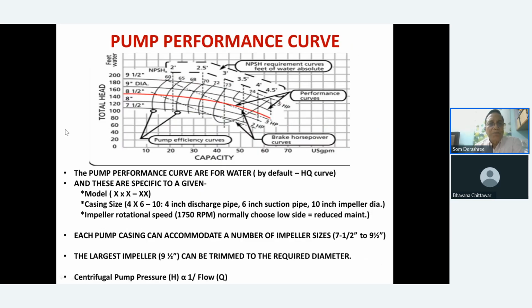Now, what are the pump performance curves? Pump performance curves are basically HQ curves, which also give you efficiency. These are all the curves for different diameters. This is 9.5 inch diameter, this is 9 inch diameter, 8.5 inch diameter, 8 inch diameter, and 7.5 inch diameter. And these are the parallel lines. So as you move up, the diameter increases.